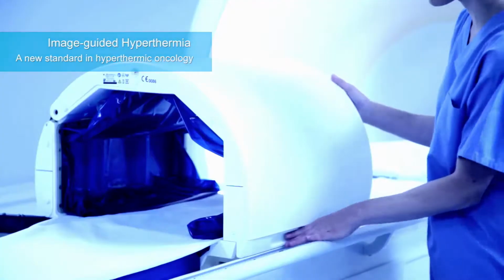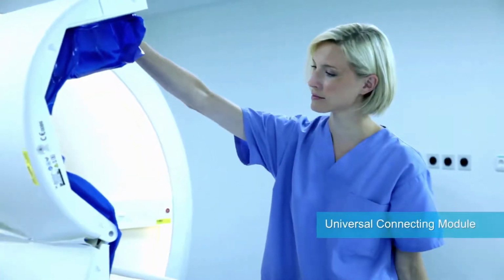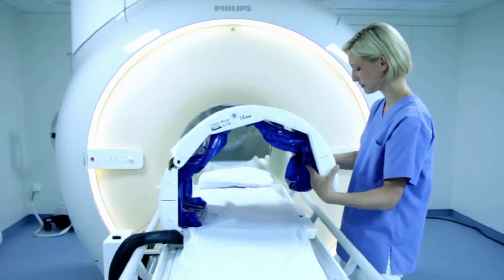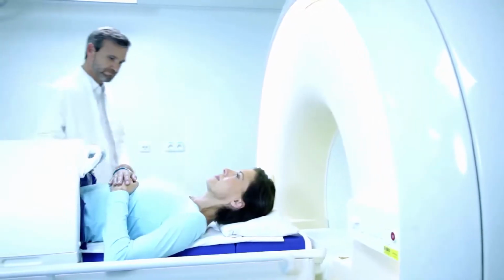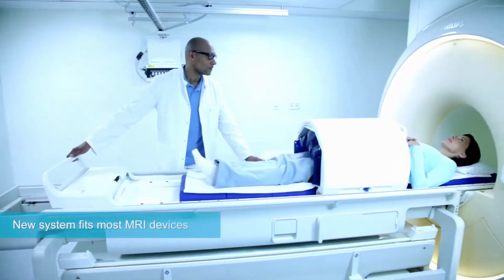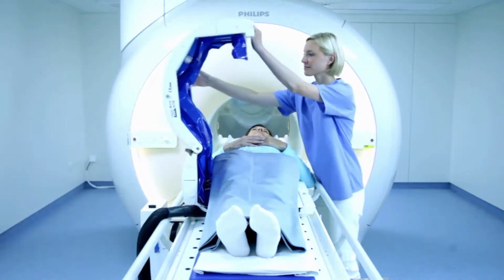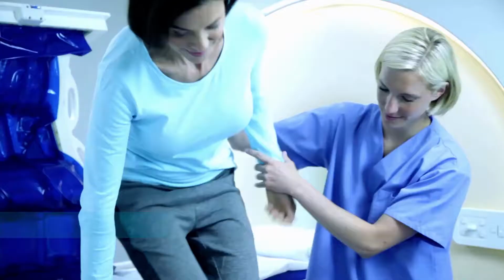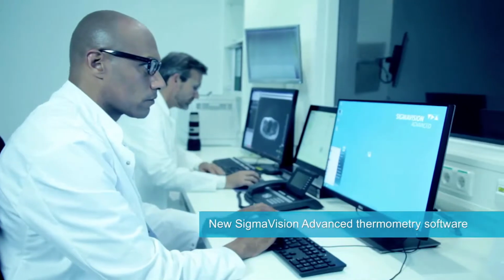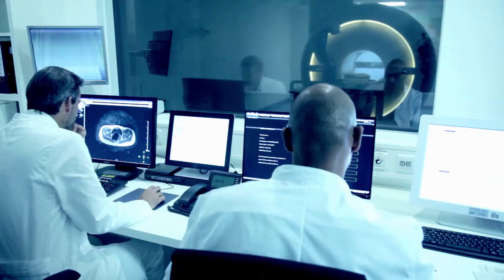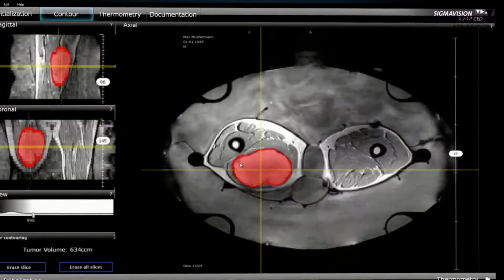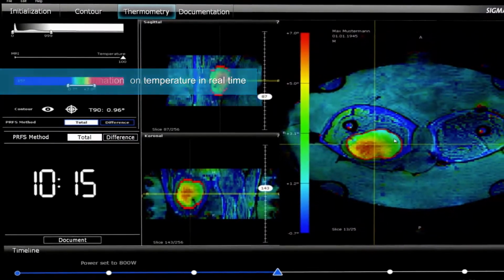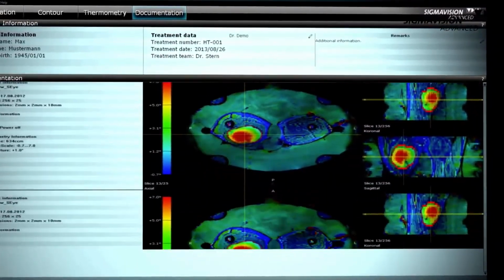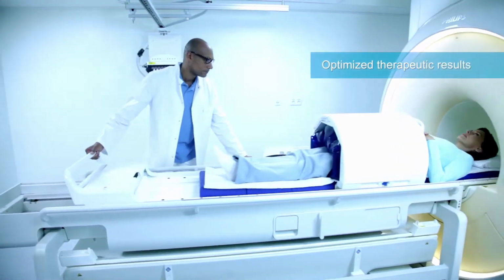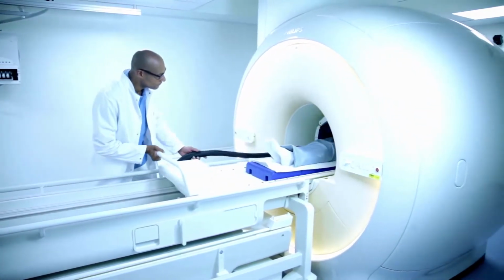Hybrid hyperthermia is a further technological development of regional deep hyperthermia. Our combined certified devices meet the demand for a universal connecting module that allows cancer centers to operate their MRI devices with hyperthermia systems. The patient applicator fits most 1.5 Tesla MRI systems with 60 centimeter bore and larger, while its side entry allows for easier setup and improved patient comfort. We supply the corresponding hyperthermia control software. Sigma Vision Advanced is a completely new thermometry software, enabling users to measure, monitor, and document temperature changes during hyperthermia treatment. MR image-guided hyperthermia provides non-invasive, three-dimensional temperature imaging during the course of treatment, leading to optimized therapeutic results.